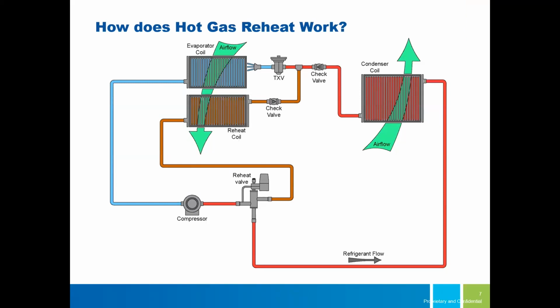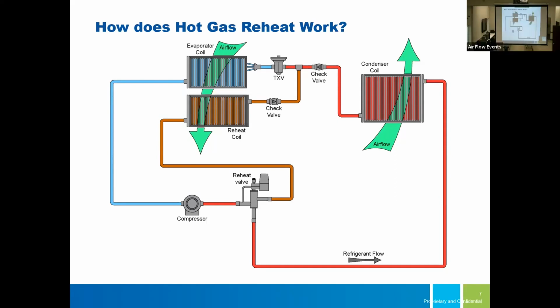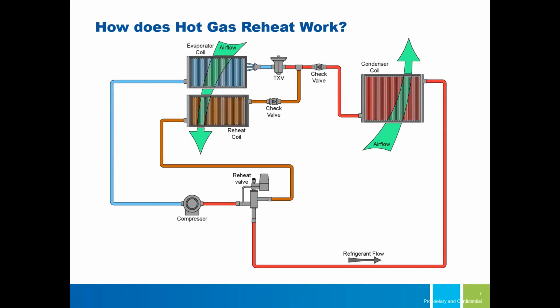Oh, so you're talking coming off the coil. Are you talking about leaving the unit in dehumidification at 60 degrees? After the reheat coil, trying to hold 62, 61, 63, 60, something like that. How manageable is that with the hot gas reheat system? I think it's possible, but I would be honest, you're kind of going outside of my expertise.